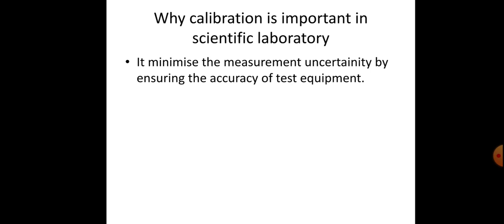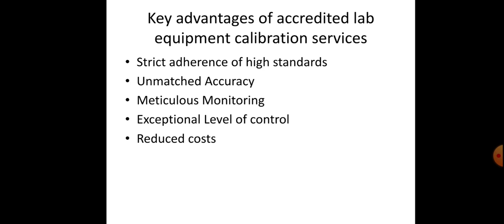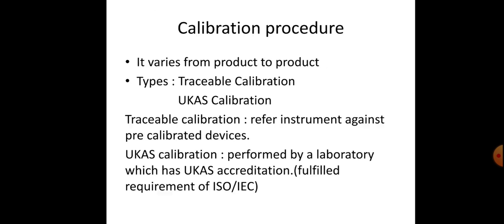Why is calibration important in a scientific laboratory? It minimizes the measurement uncertainty by ensuring the accuracy of the test equipment. Key advantages of accredited lab equipment calibration services: generally the labs are accredited by the NABL, the National Accreditation Board for Testing and Calibration Laboratories. When these labs are accredited, there is strict adherence to high standards, unmatched accuracy, meticulous monitoring, an exceptional level of control, and reduced cost. So these are the key advantages when a lab gets accreditation.